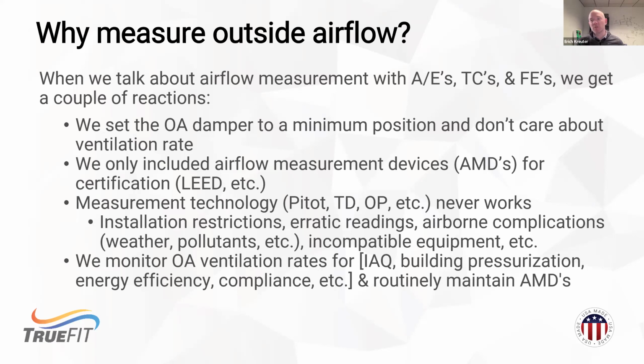On the other end of the spectrum, people that are interested in high performance sequences a lot of times find that the existing technologies out there, whether it's pitot arrays or, as Matt mentioned, measurements installed in turbulent locations such as hoods or too close to louvers, don't produce the results needed to really drive those high performance building sequences where we want fairly precise control over pressurization and resulting ventilation. So both sides of the spectrum have issues today. Generally we're either losing OA on energy efficiency or we're losing it on system performance.